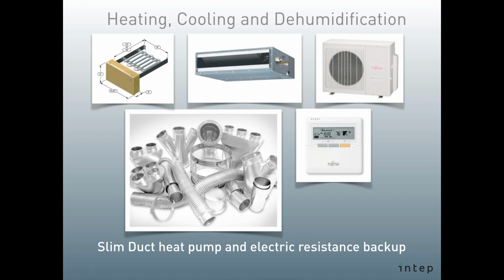They have a fully programmable thermostat, and on the upper left-hand corner, you can see an electric resistance heating coil. Why do we have that? Simply because our lowest design temperature of the year exceeds the capacity at which the outdoor compressor is still allowed to run for this kind of system. So we can get down to, I want to say, about 13F or maybe a little lower, but then at some point there is a handover to the electric resistance system. So ultimately on the coldest days of the year, there'll be some electric resistance input. During all the other times, there'll be a coefficient of performance that comes out of using a heat pump.